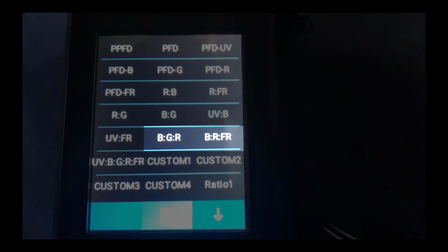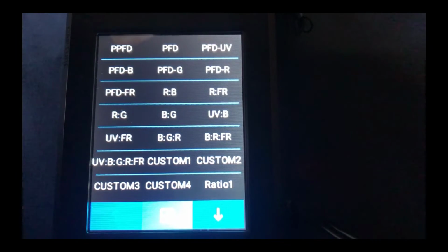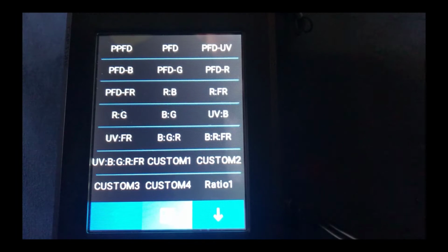Now, while you can't compute a ratio when you have three variable wavebands, what the instrument will do is break down the light into the fraction of light from each of those wavebands. And you'll notice we also have one over here, one final ratio, which actually breaks the light down into all 5 wavebands, so you know the percentage of light coming from each of those. So those can be very useful for trying to grow your plants and control what's happening inside your greenhouse or growth chamber.